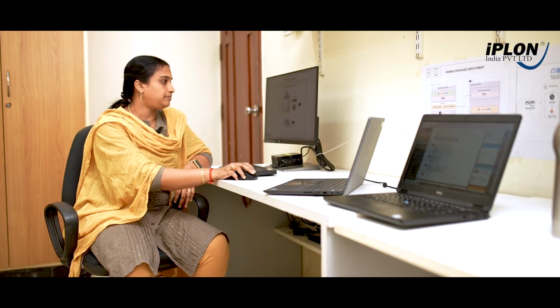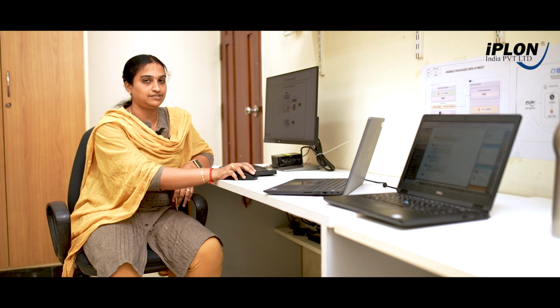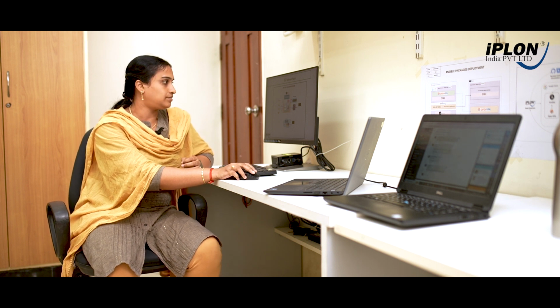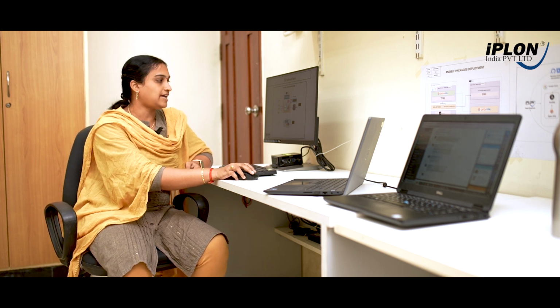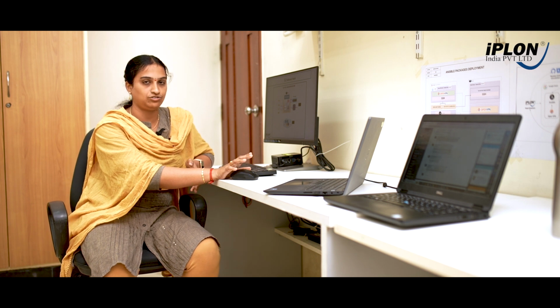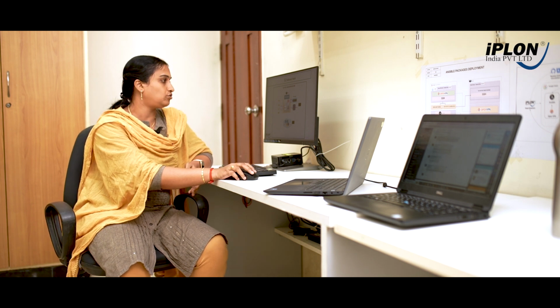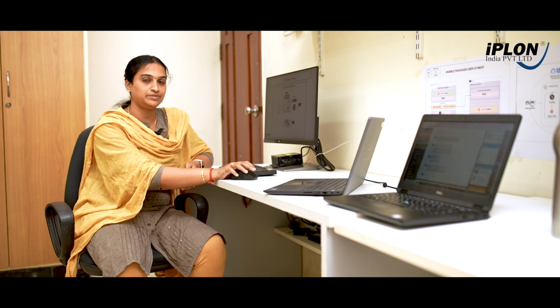And there will be a Modbus virtual server running inside our server, which acts as the bridge between the PPC controller and the field devices. Whatever data is read from the field devices is sent to the PPC controller through the Modbus virtual server, and the controlling from the PPC controller is also done through this virtual server. This complete flow runs on the Edge.